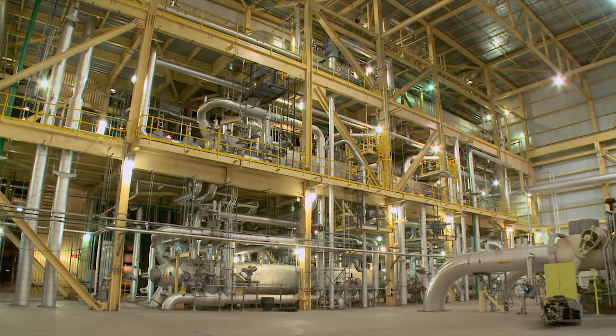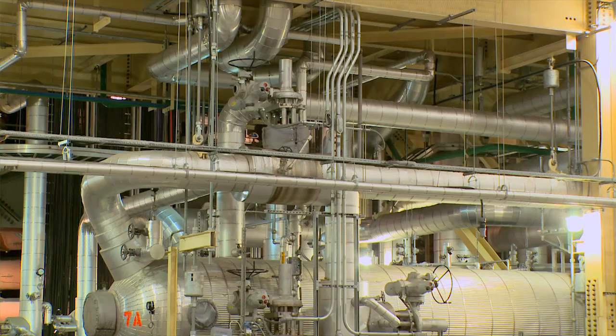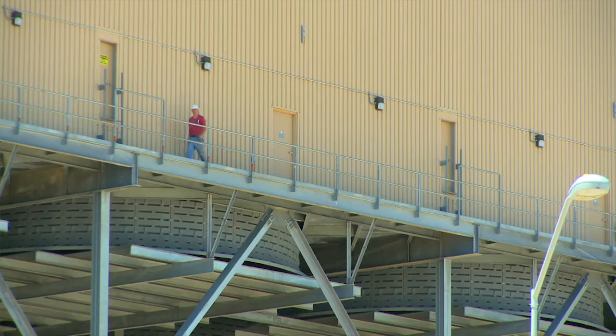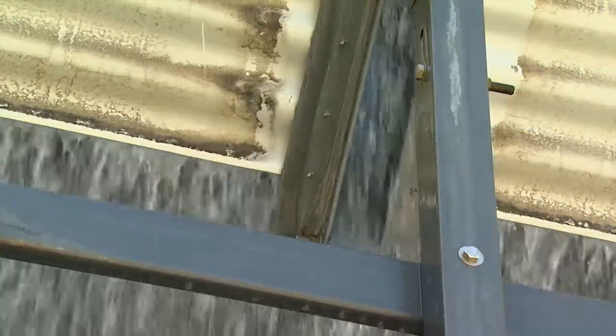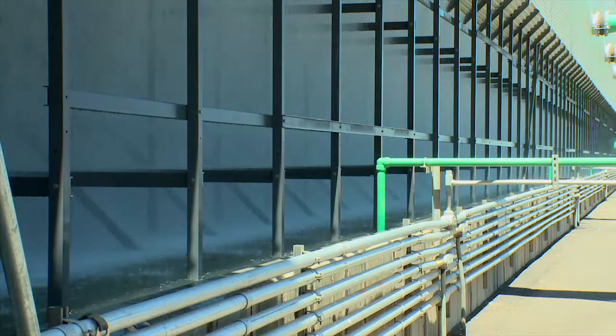We could operate Unit 3 with just the air-cooled condenser. In the wintertime, we could probably still sustain full load on the system. In the summertime, it's going to drop off significantly. We'd probably be lucky to be at half load just on the air-cooled condenser on days when we're up in that 90-degree range. During the hot summer months, air cooling is just not enough.